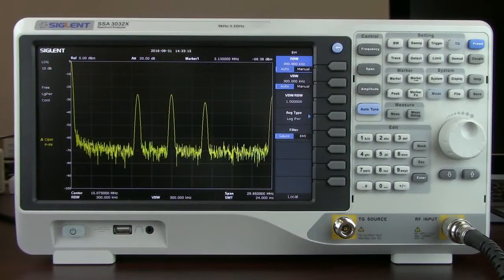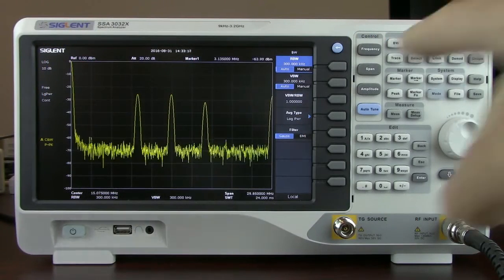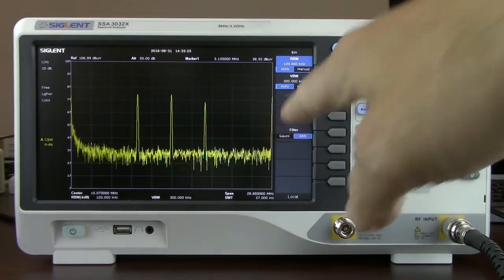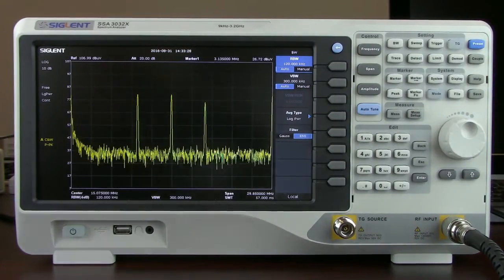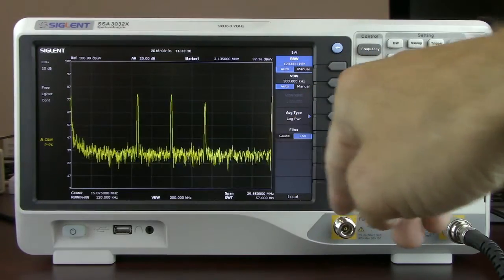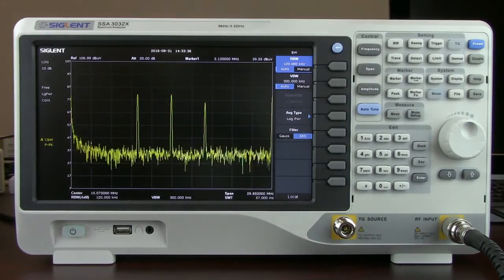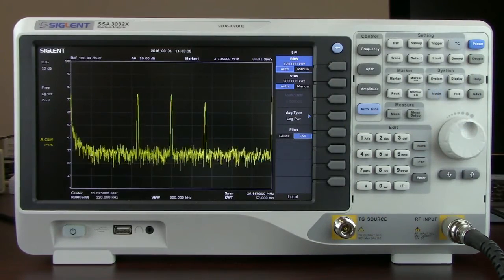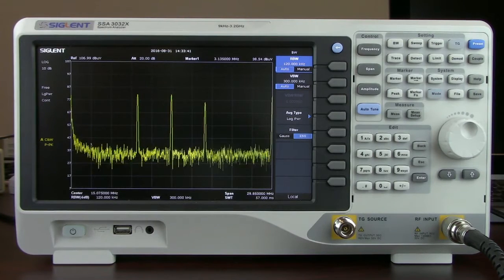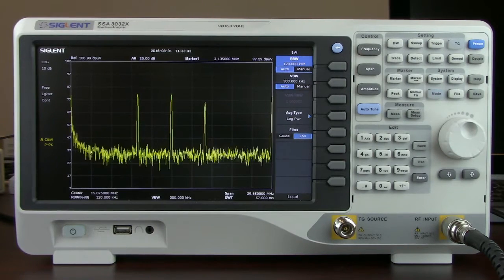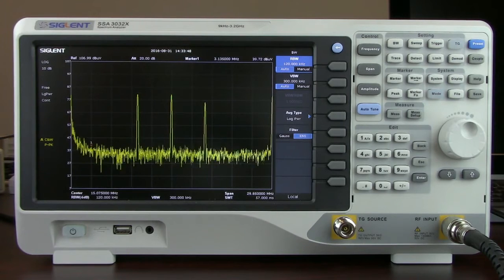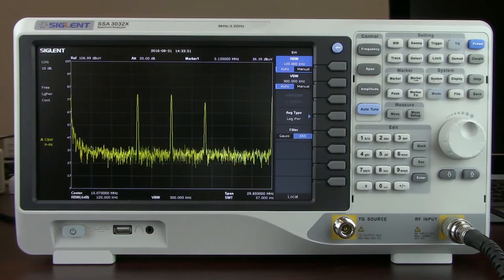Some of the things that come with this feature are the EMI filter. We can enable that by pressing the bandwidth key and then enabling EMI. Once you've enabled the EMI filter, that's a 6 dB filter as compared to the normal 3 dB Gaussian filter. That 6 dB EMI filter then enables you to select resolution bandwidths of 200 Hz, 9 kHz, and 120 kHz. Those are defined bandwidths for the FCC as well as CISPR measurement standards for compliance.